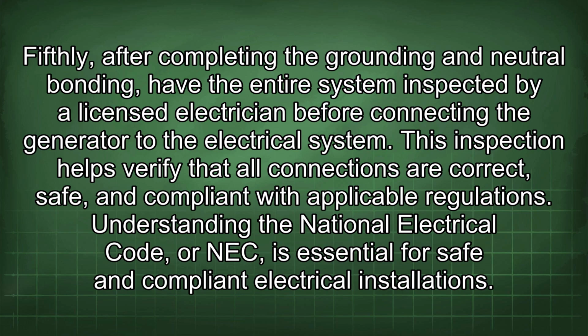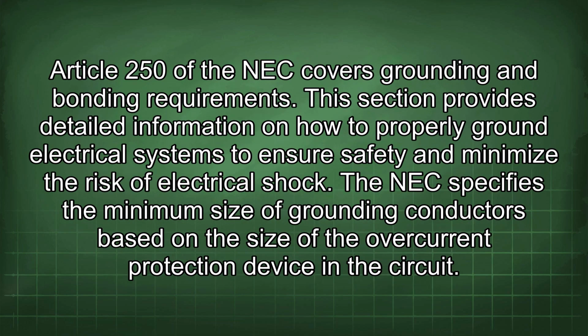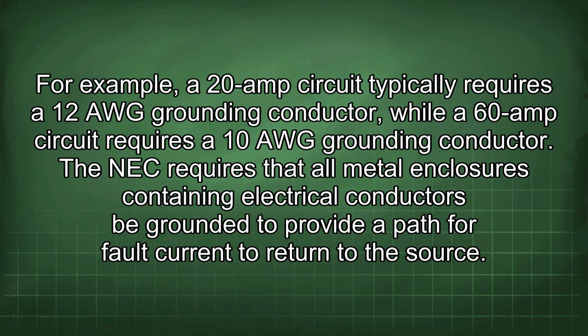Understanding the National Electrical Code, or NEC, is essential for safe and compliant electrical installations. Article 250 of the NEC covers grounding and bonding requirements. This section provides detailed information on how to properly ground electrical systems to ensure safety and minimize the risk of electrical shock. The NEC specifies the minimum size of grounding conductors based on the size of the overcurrent protection device in the circuit. For example, a 20 amp circuit typically requires a 12 AWG grounding conductor, while a 60 amp circuit requires a 10 AWG grounding conductor.